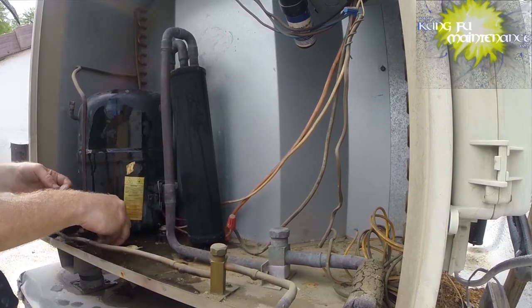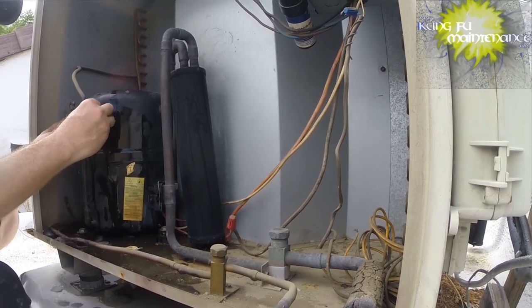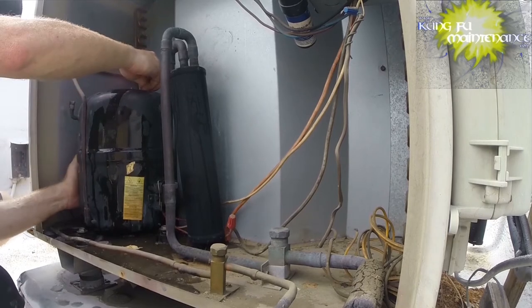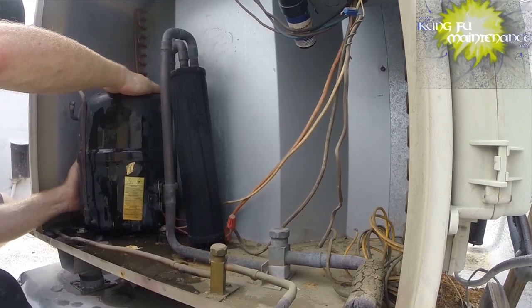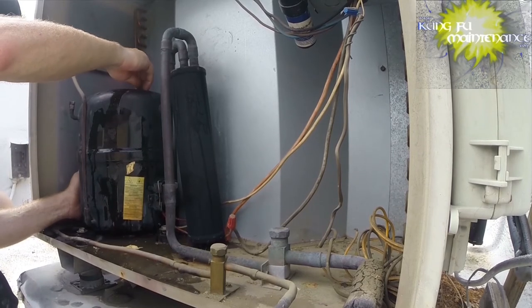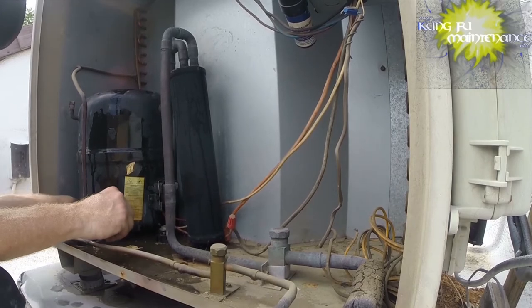And again, the formula is 2650 times full load amps divided by voltage equals capacitance. That's 2650 times the running amps divided by voltage equals capacitance.